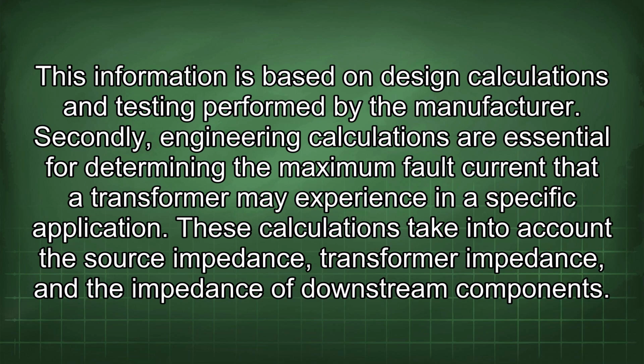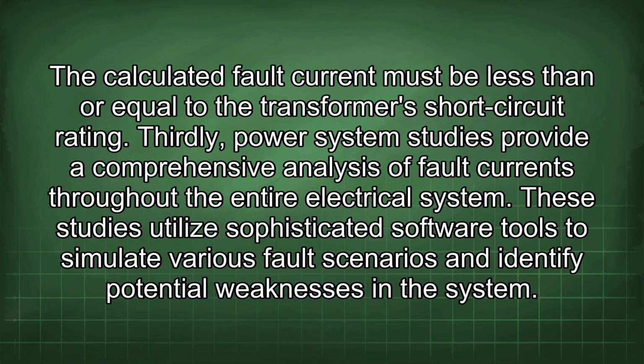This information is based on design calculations and testing performed by the manufacturer. Secondly, engineering calculations are essential for determining the maximum fault current that a transformer may experience in a specific application. These calculations take into account the source impedance, transformer impedance, and the impedance of downstream components. The calculated fault current must be less than or equal to the transformer's short circuit rating.